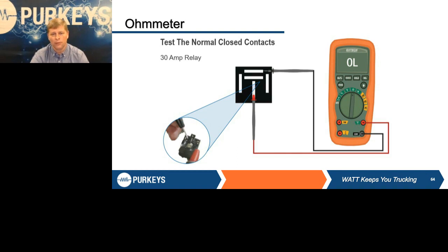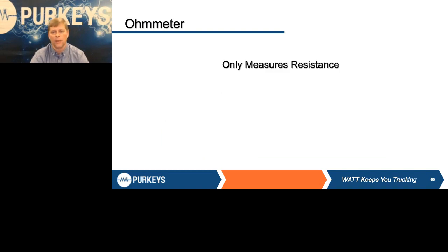So what does an ohmmeter do? It simply measures resistance. And you have to understand what that meter tells you. Is it a straight reading? Is it a kilo ohm reading? Is it a mega ohm reading? And this is one of the things that tell you that you've got to be careful what kind of meter you buy. I've had technicians that couldn't test anything because their meter only had a capacity of 4,000 ohms. So even that first example for that sensor, anything it did is going to show OL because it doesn't have the capacity to even read up to the 6,000. So you do have to be careful what you are using, and whether it is a quality meter.